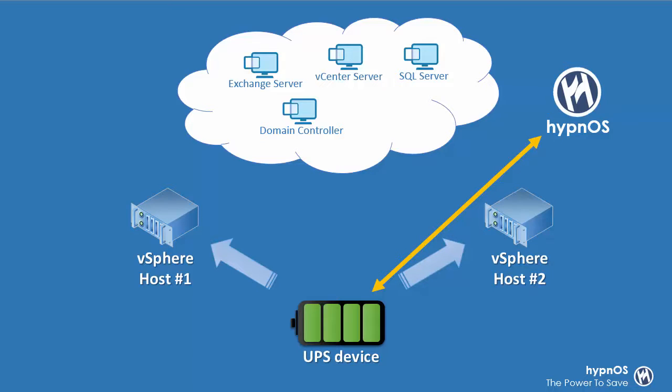HypnOs talks directly without any further application layer to the UPS through SNMP, Simple Network Management Protocol. A protocol almost every UPS system is able to handle. It also talks not only to the vCenter server, but in addition directly to every vSphere host. This communication is done without the help of any helper appliances or software stacks. We directly communicate through the VMware API, which is fast and reliable.